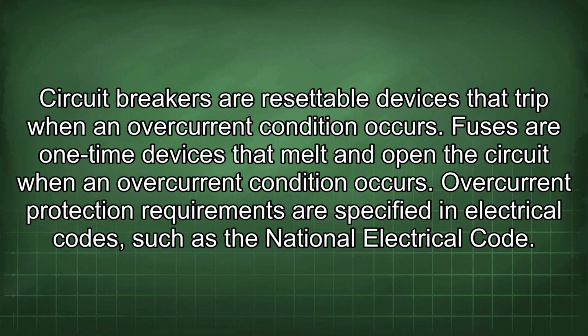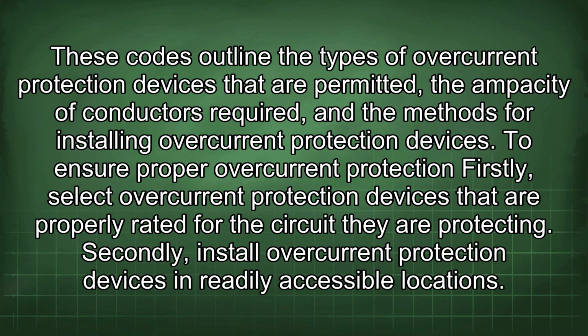Circuit breakers are resettable devices that trip when an overcurrent condition occurs. Fuses are one-time devices that melt and open the circuit when an overcurrent condition occurs. The overcurrent protection requirements are specified in electrical codes, such as the National Electrical Code. These codes outline the types of overcurrent protection devices that are permitted, the ampacity of conductors required, and the methods for installing overcurrent protection devices.